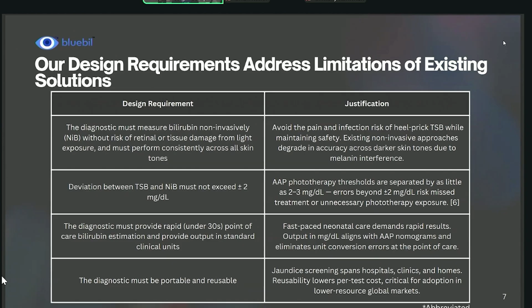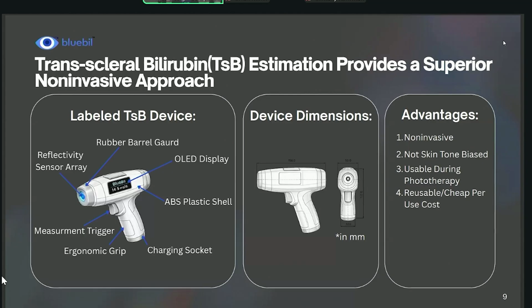This is our actual device over here, and it uses controlled light and reflective optics to measure bilirubin content, and it has an ergonomic grip, a measurement trigger, and an OLED display. We determined these designs to make it as easy as possible to use for nurses, and require minimal training. The advantages of this are that it's non-invasive, it's non-skin tone based, it's usable with the current phototherapy treatments, and it's reusable, with a cheap per unit cost.